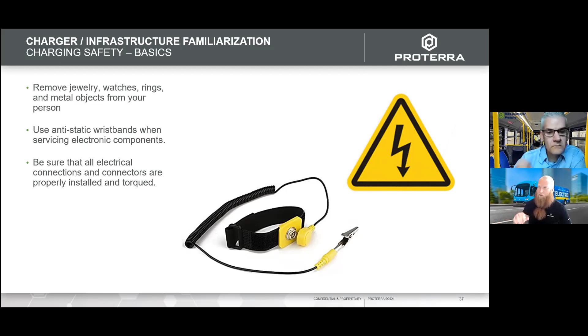So if a technician is doing any sort of visual inspection, I usually tell them, as long as the device has been locked out entirely and you've confirmed there's no voltage, do your test touch on all of the connectors and make sure that everything is properly seated.